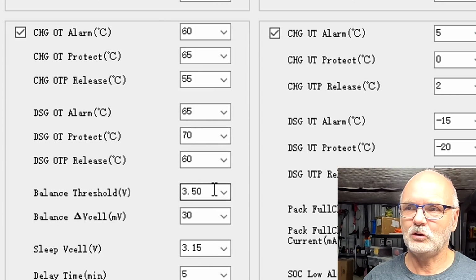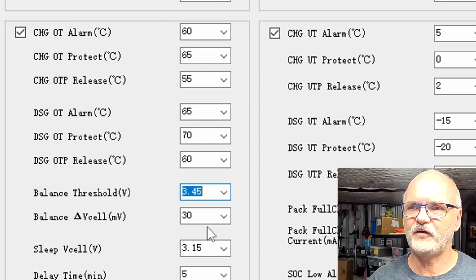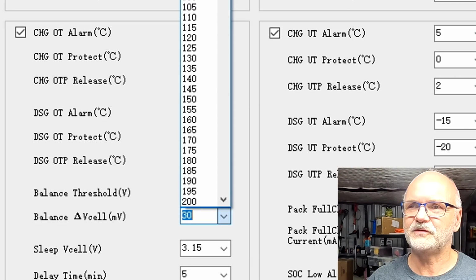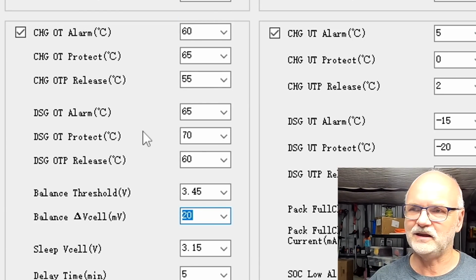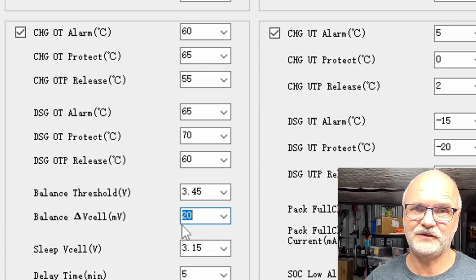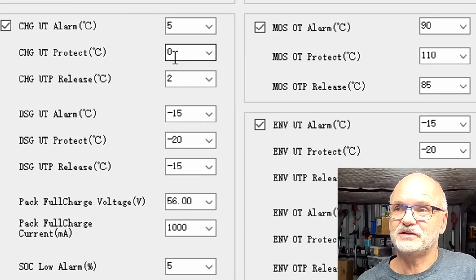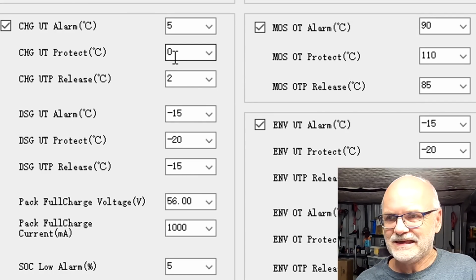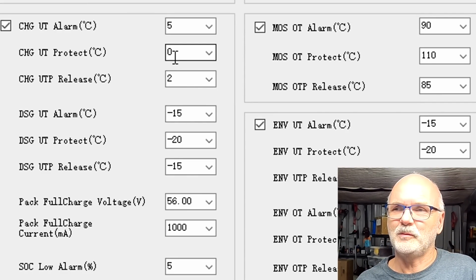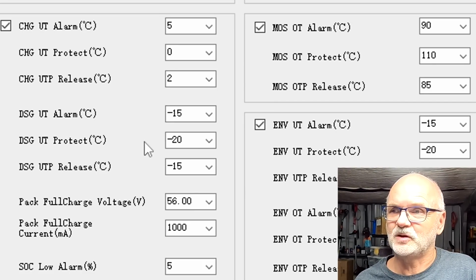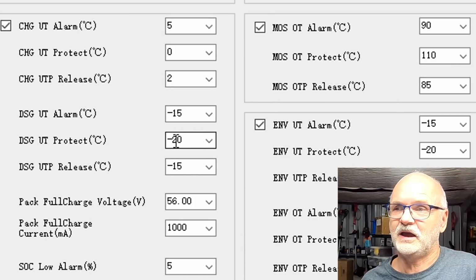The balance threshold, I will set this one to a 3.45. And I want the precision to be as low as possible. If the balancer kicks in, let it balance. 20 millivolt difference is the smallest I can set. So it allows us to charge down to 0 degrees Celsius. Even this is per specifications. I would probably set this one to 5 degrees. And here the discharge under temperature protection at negative 20 degrees Celsius is as per specifications.